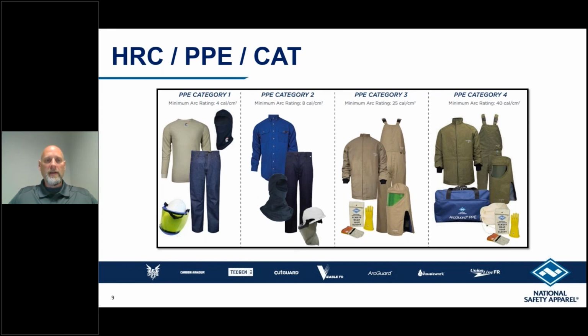For Cat 1, you're talking about complete protection head to toe. The clothing needs to be flame resistant and needs to have an arc rating of at least 4 calories. That's a measurement of incident energy that it must sustain without igniting or allowing somebody to have serious injury. And Cat 2 is 8 cal, same thing, head to toe. Cat 3, 25 cal. Cat 4, 40 cal.